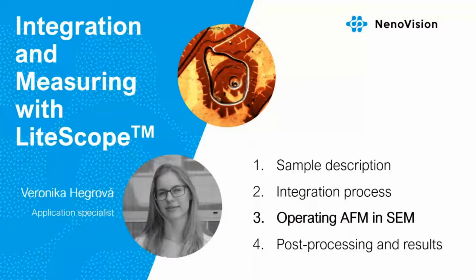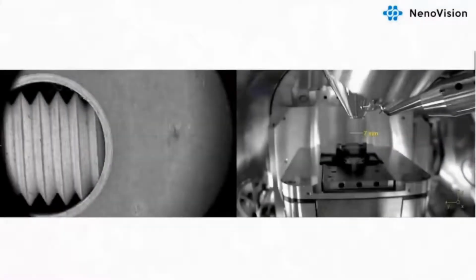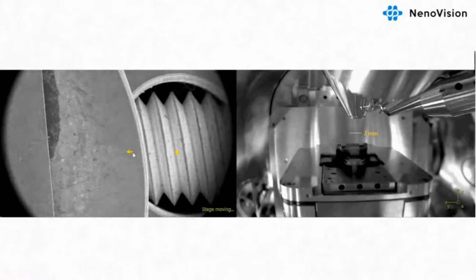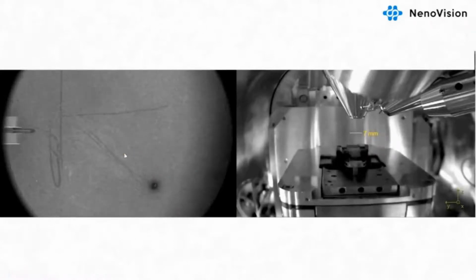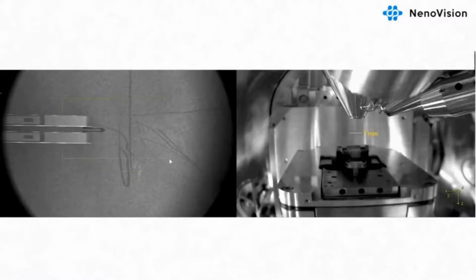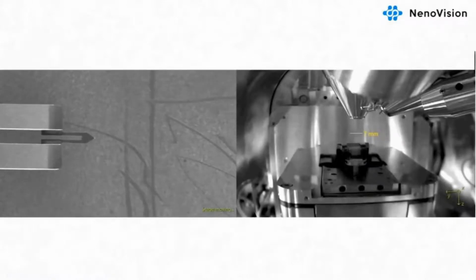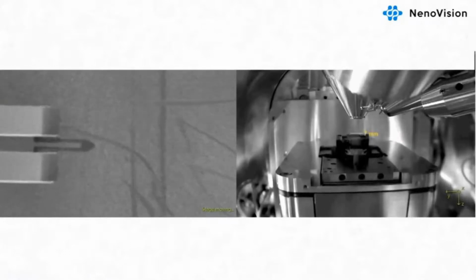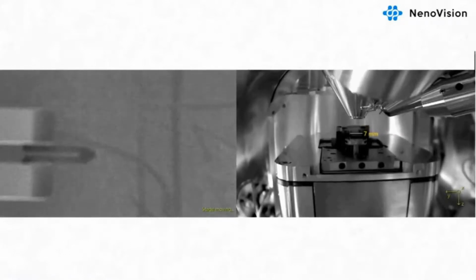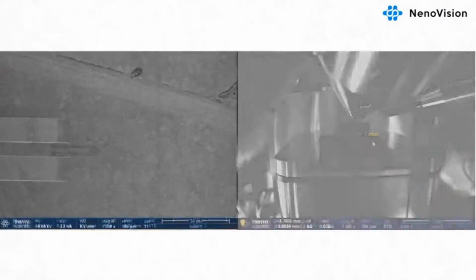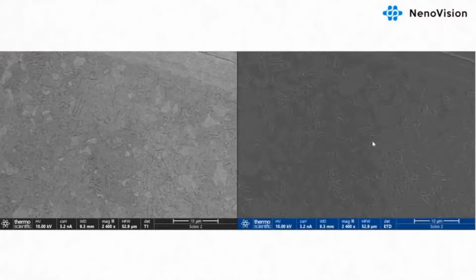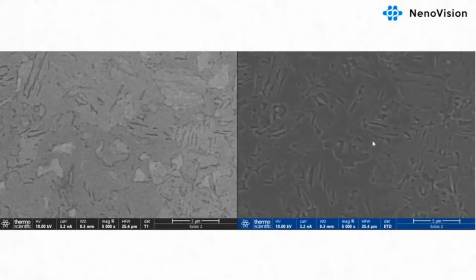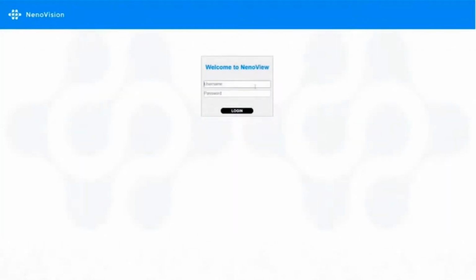Now we are going to have a look how to measure AFM and SEM together. During the pumping, we move the LiteScope under an SEM cathode. As I skipped SEM adjusting, because it works the same way as SEM alone, I can also safely come closer to the cathode in a Z direction. We find an interesting spot on the sample for us and improve focus.